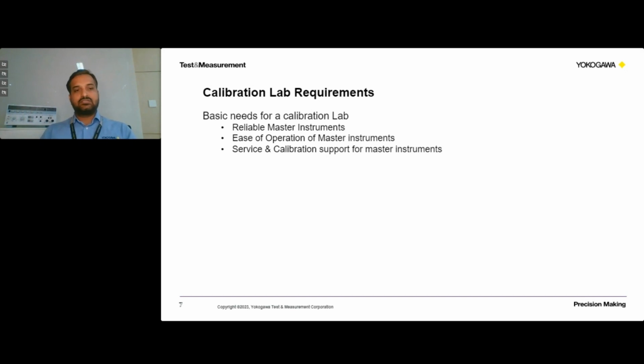The master instrument should not involve much complexity in operation, and it should be easily operable, so that much of the time can be saved with respect to calibration of the DUTs. And service and calibration support for the master instruments: any master instrument available in the calibration lab should have very minimal and well-regulated service and calibration support, so that the downtime of the calibration can be reduced. So there should be easily available service and calibration support.